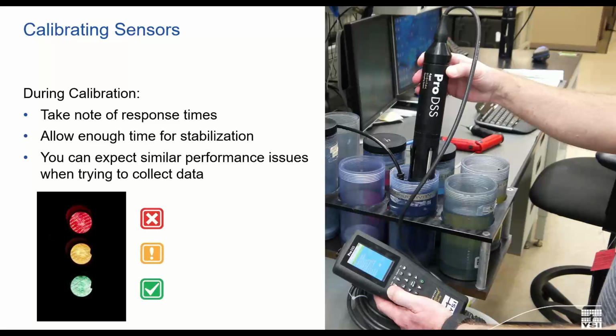A green Smart QC score means the sensor is calibrated properly and all parameters used to assess its performance are within factory specification. A yellow Smart QC score means that the sensor will still perform within factory specifications, but that during calibration, enough of an adjustment was required to suggest that the sensor is drifting from those limits or may soon require some adjustments, such as a new DO membrane cap or a new pH electrode. You might want to go back through the calibration process just to make sure you did all the steps properly. But in all cases, a yellow QC score is not an indication that that sensor is performing outside of specifications.